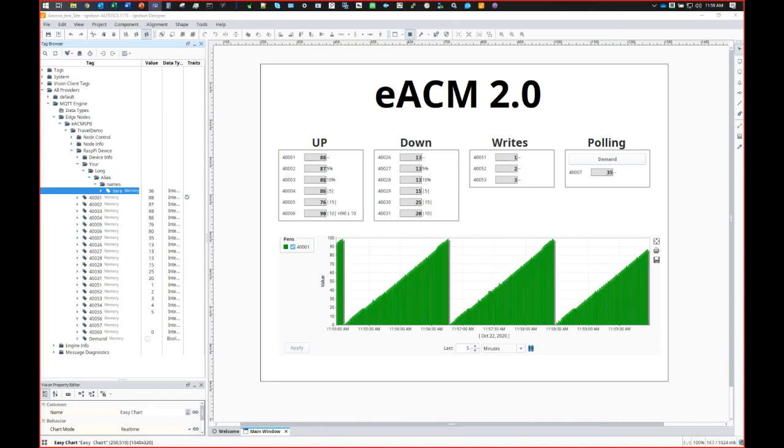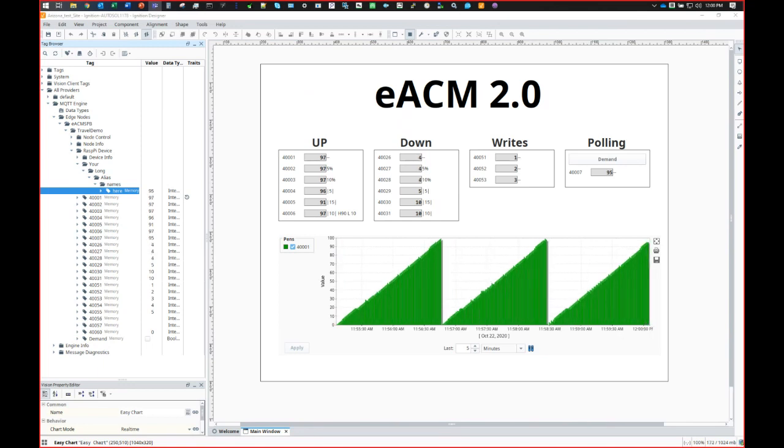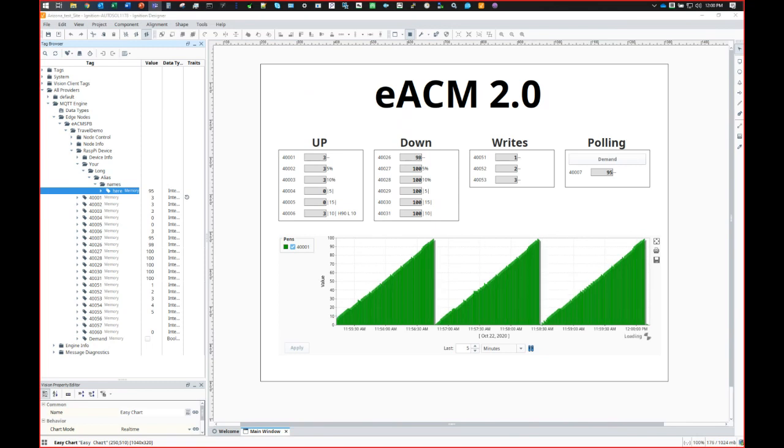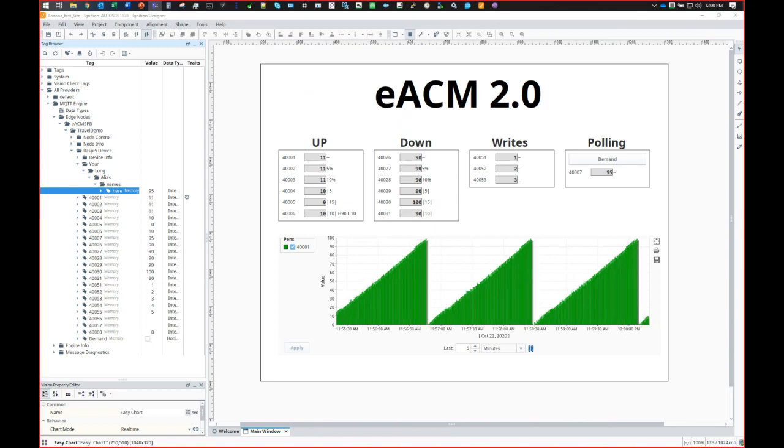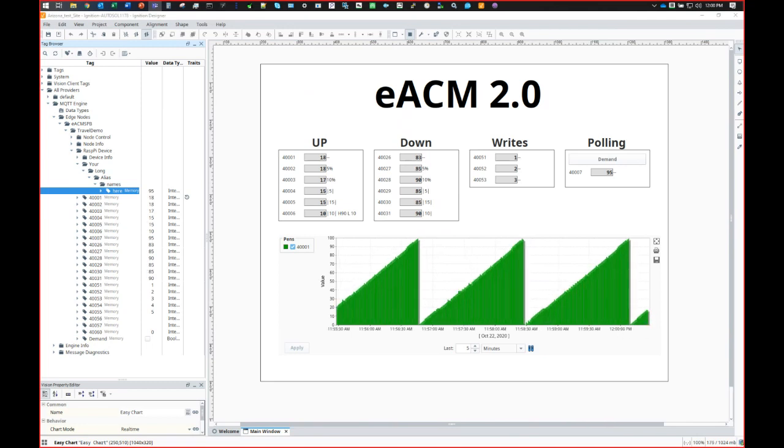Can eACM collect measurement data, archive data, then provide a CFX file? The answer to that is no, but here's why. eACM will collect the data and send it via MQTT to an ACM on the server. So for EFM, you have to use ACM because there is not a public standard for EFM collection over MQTT. We are creating that public standard currently. So basically, eACM collects EFM data and sends it to ACM. ACM gathers it, puts it in a SQL database, and from there you can then provide a CFX file.